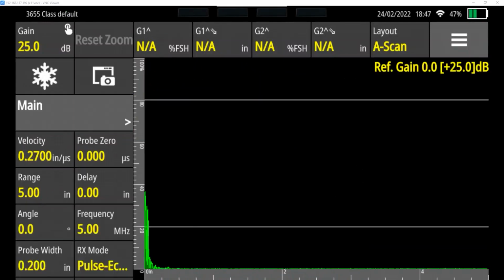If you want more detail on this, I would recommend watching the video I did on setup and calibration using a 5-step block, where I go into this in detail. But I'm going to leave my velocity off a ways so that we can see how this works. Normally for aluminum, we would preset it to about 0.2500 or 0.2490. But by starting at 0.270, it gives me a little bit of room to explain the calibration process. Probe zero will start at 0 microseconds. We'll change that after we've got the velocity set.